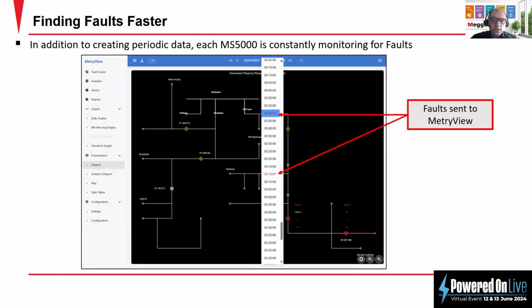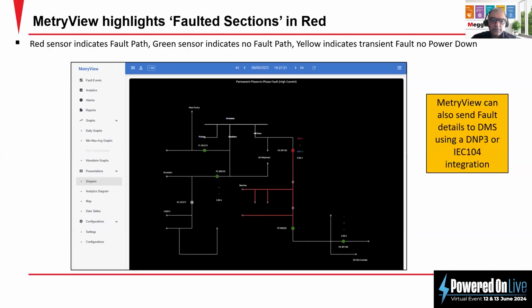And the sensors create the periodic data, and all the time they are monitoring for faults, and they're recording each fault. By clicking on the top of the software, you can find the time, where the black one shows the normal operation of the network, and the red one records the faults. By clicking on each red dot, you will get the fault information. This includes which part of the network is faulty, and which sensors are sensing this. And then this can be sent to the utility DMS.